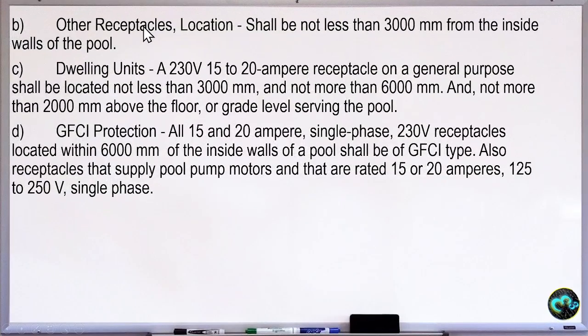Okay, so other receptacles location shall be not less than 300 mm from the inside wall of the pool. So lahat ng mga receptacle, no, shall be not less than 3,000 mm, no, inside the walls of the pool. Dwelling units, no, so at 230 volts, 15 to 20 amperes receptacle on a general purpose shall be located not less than 300 mm and not more than 600 mm and not more than 200 mm above the floor or grade level of the serving pool.